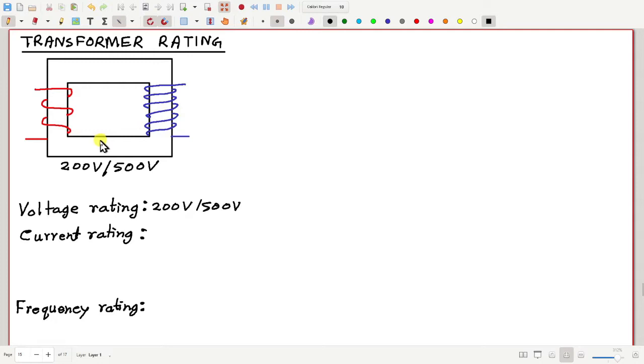We cannot use this transformer with any higher level of voltages, because if we do that, the transformer may get damaged, it may cause dangerous accidents. Why? Because if these two ends of this winding are at two different voltages, suppose this end is at 0 volt and this end is at 200 volt at some point of time, that means the in-between turns are also at different voltages, like for example, this point may be at say 80 volt, this point may be at say 160 volt, and this may be at 200 volt, and so on.